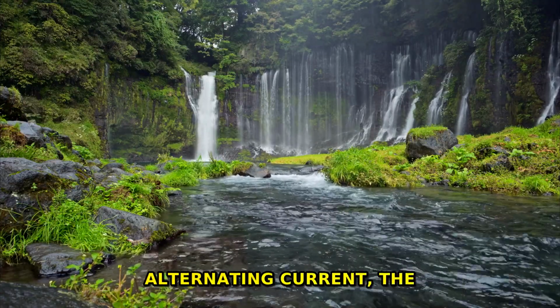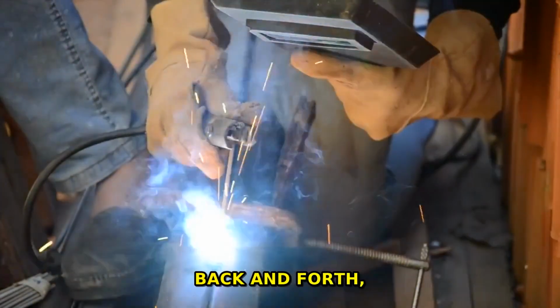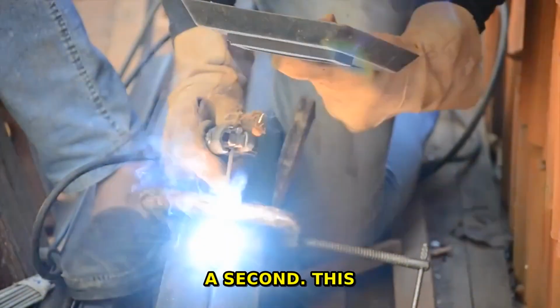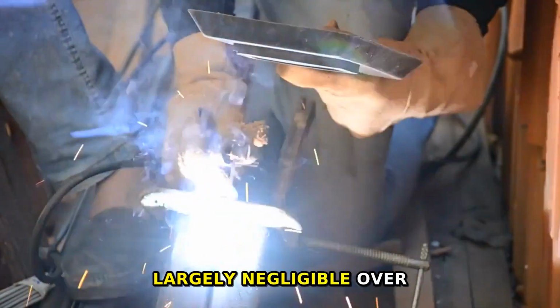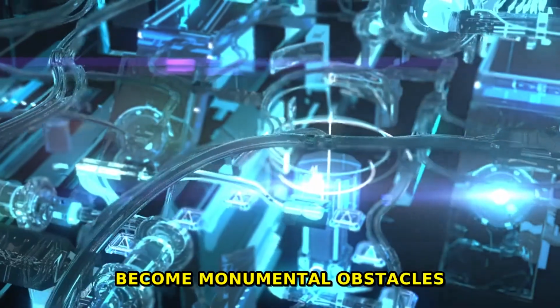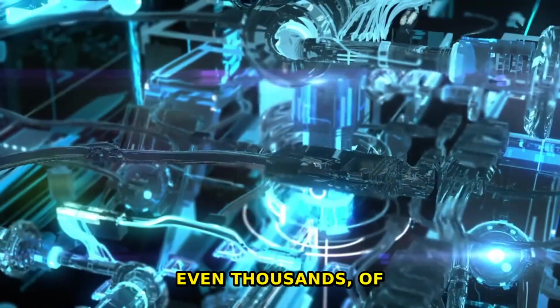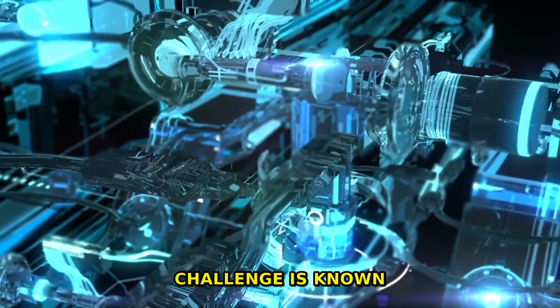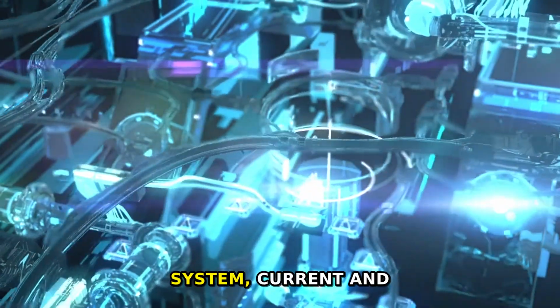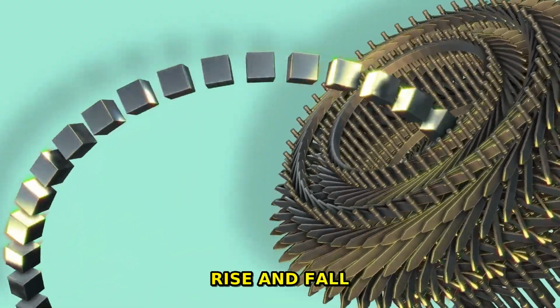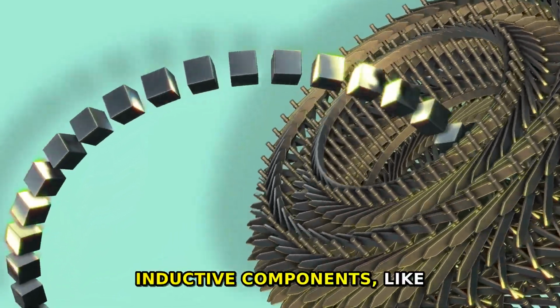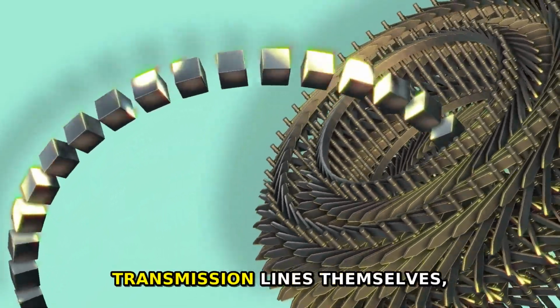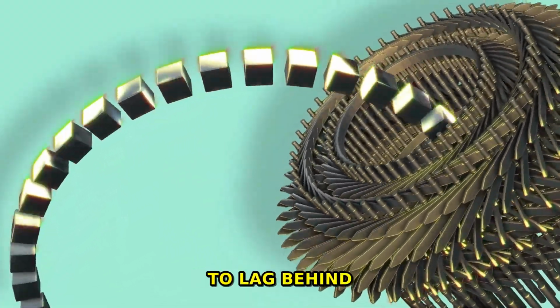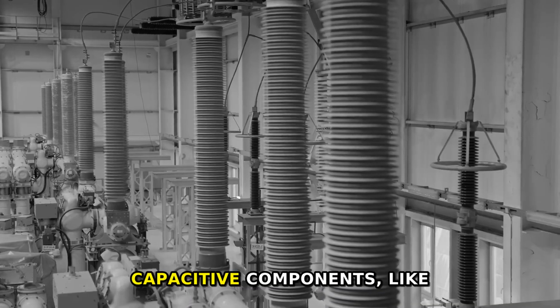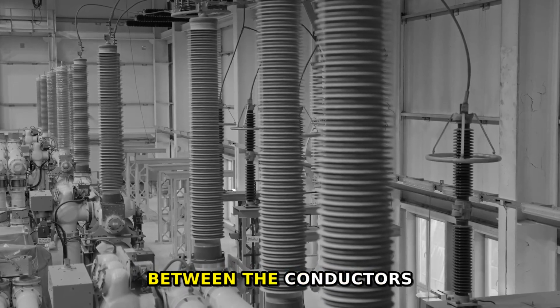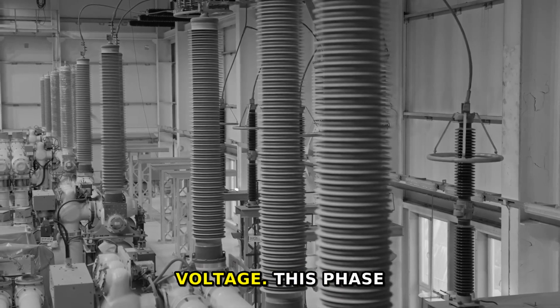With alternating current, the water isn't just flowing, it's oscillating back and forth, hundreds of times a second. This constant reversal creates problems that are largely negligible over short distances but become monumental obstacles over hundreds, or even thousands, of kilometers. The first challenge is known as reactive power. In an AC system, current and voltage don't always rise and fall perfectly in sync. Inductive components, like the magnetic fields generated by the transmission lines themselves, cause the current to lag behind the voltage. Conversely, capacitive components, like the electric fields between the conductors and the ground, cause the current to lead the voltage.